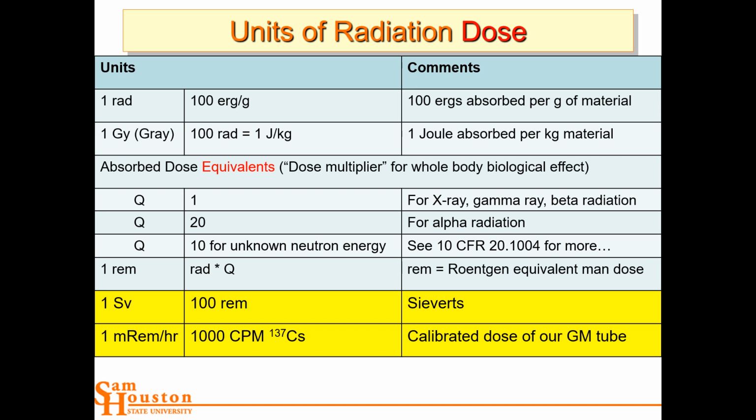So essentially this radiation monitor that we have in the lab is measuring the radioactivity of the Fiesta plate and the smoke detector as if it were cesium-137. So that's an assumption that's built into that detector. But those aren't cesium-137. Now, in terms of the activity and the types of radiation that they emit, it's an okay assumption. But you just need to know that if you were dealing with something completely exotic, a really high energy emitter or something like that, then that assumption might not be very valid. But this is a good, safe assumption that we can use.